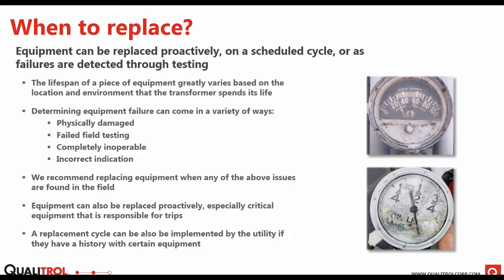And if it's close, it could be calibrated. And if it's not, then there could be a bigger issue with the unit. And that could be any gauge, not just a Qualitrol gauge. It could be any old GE gauge like we have here, or an old liquid level gauge, if there are any issues with contacts, anything like that. So we recommend replacing it when any of the above issues are found, and especially if it's hooked into an alarm circuit, trip circuit, or control circuit.